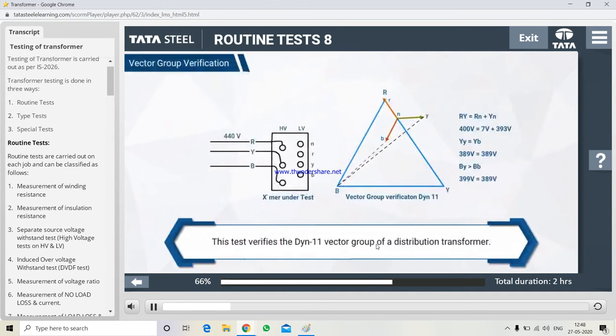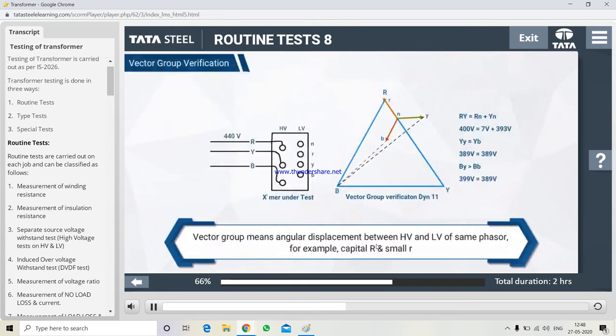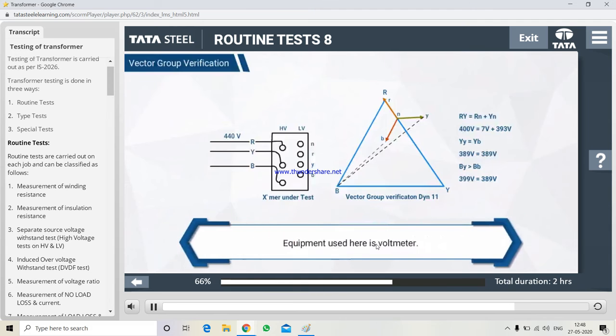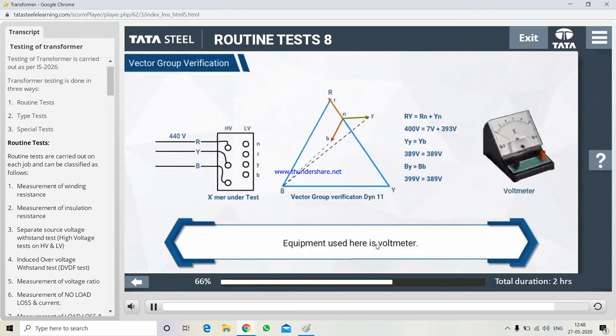This test verifies the Dyn11 vector group of a distribution transformer. Here, vector group means angular displacement between HV and LV of same phasor. For example, capital R and small r. Equipment used here is voltmeter.